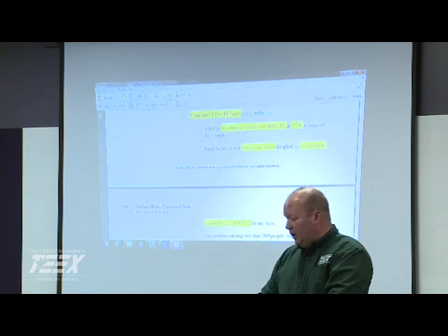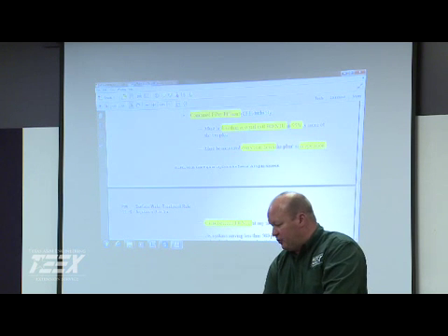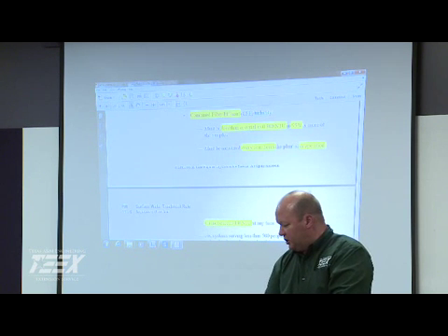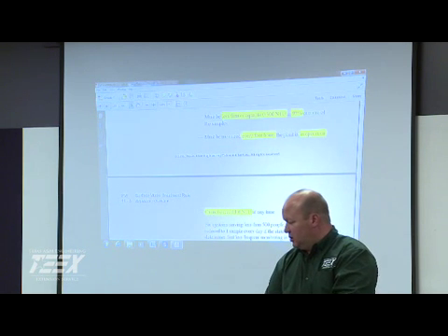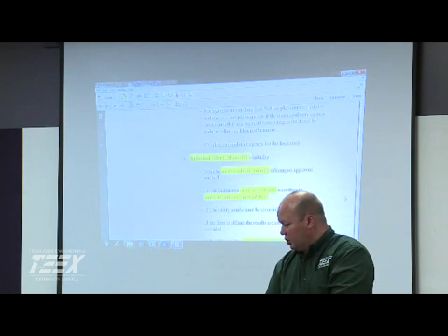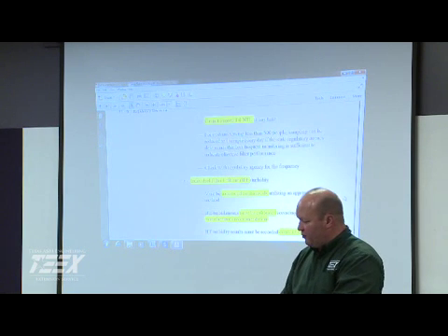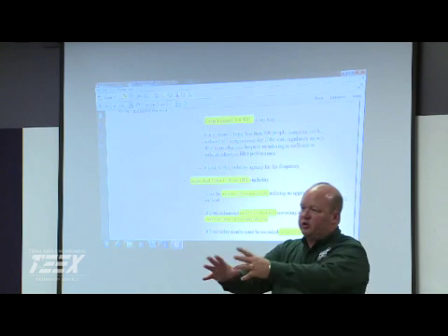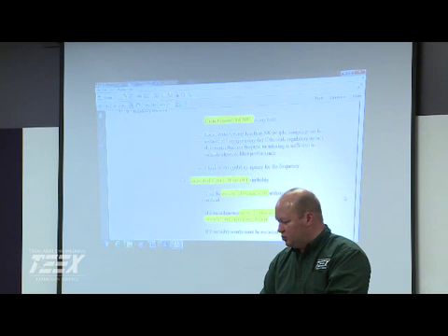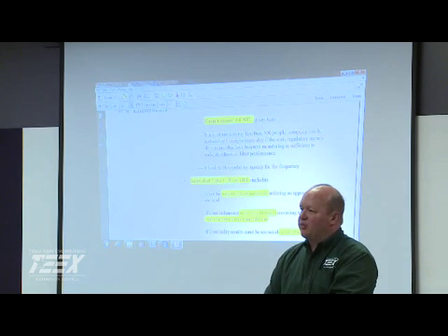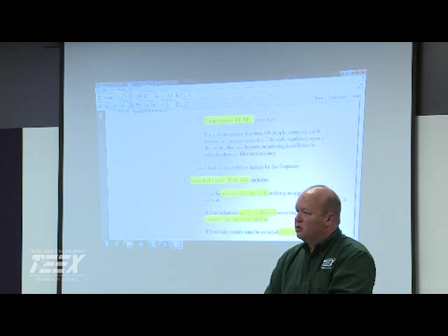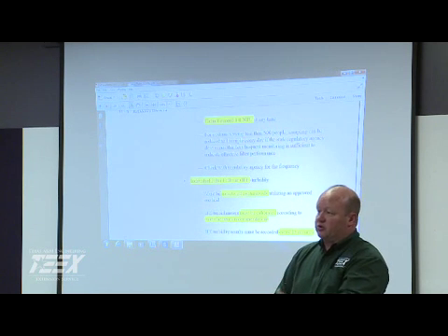All right, combined effluent. So it can't have more than 1 NTU. You've got to do it every 4 hours that we're in operation. And there's a little provision there for 500 people or less, where with state approval you can go down to just once per day. I don't know if anybody's treating that small amount of water off of a surface water source.